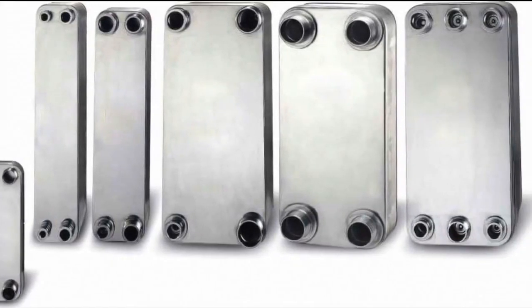In that case, nickel exchangers must be used. Nickel exchangers have limits on pressure: while a copper-brazed plate heat exchanger can easily reach 30 bar or even higher pressures, the nickel exchanger has a lower resistance to pressure. The standard heat exchanger handles 16 bar, and there are versions up to 25 bar, so one must be cautious where it is used. On the other hand, it has the advantage with corrosive water or fluids that are aggressive towards copper: nickel works exceptionally well. Fascinating, isn't it?